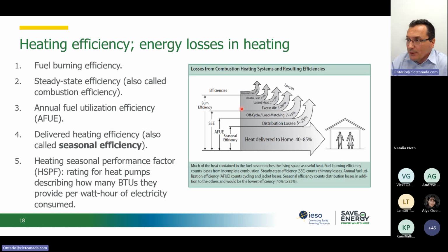In designing these combustion chambers and burners, manufacturers tend to optimize the amount of air that you add to the fuel for the full combustion. So, depending on how many molecules of natural gas you have, we need to provide a certain number of molecules of oxygen to have full combustion. And to be on the safe side, most manufacturers will design a little bit of excess air. So if we are off by a certain margin, we need to be on the safe side. So there will be a little bit of excess air. That unfortunately adds to the inefficiency of the boiler, because with that little excess oxygen, there is a lot more nitrogen from the air that passes through the boiler and then is exhausted.